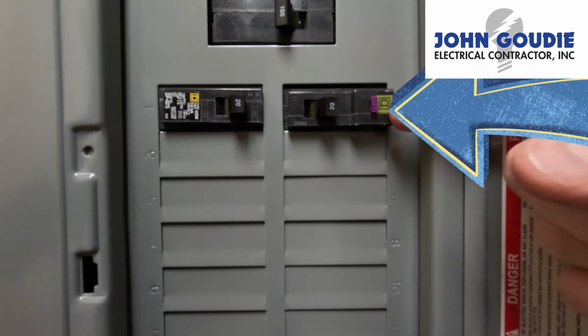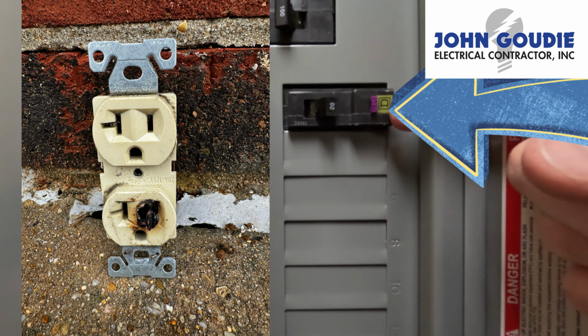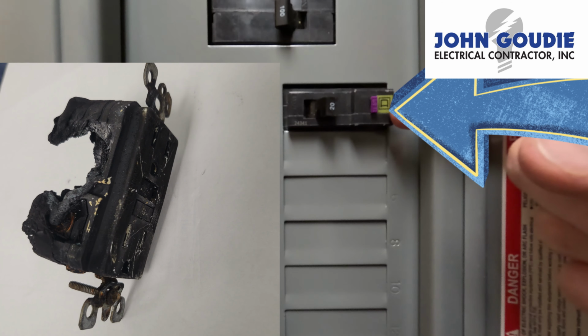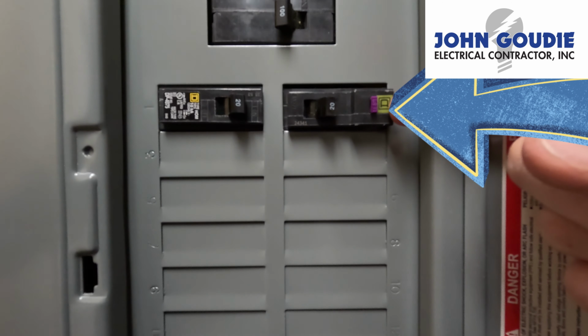So any kind of loose connection in, let's say, a duplex receptacle or a switch, a light fixture, a ceiling fan, anything that's arcing with any of those devices is going to trip this breaker. Now arcs, I'm sure as everyone knows, that's what starts an electrical fire. You'll get arcing occurring somewhere within the electrical circuit, and that's what starts the fire. So this breaker does everything that a normal circuit breaker does, but it has the added function of tripping when it senses an arc throughout the electrical circuit.